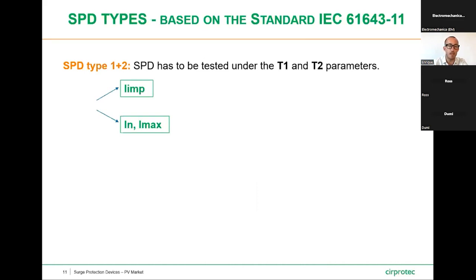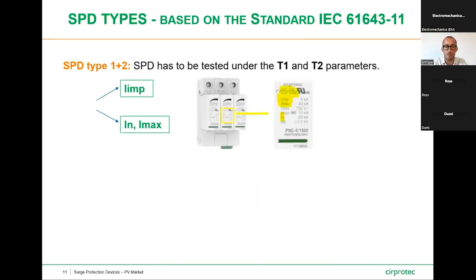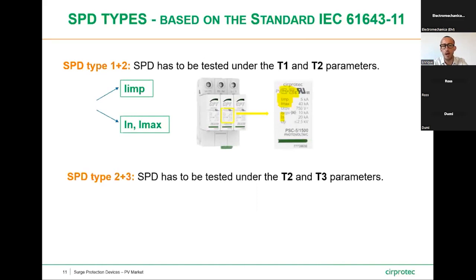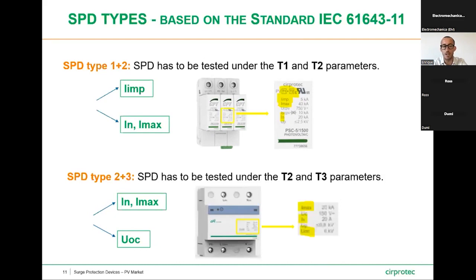For type 1, it should be shared and tested under the IGIMP, and for the type 2, the SPD type 1 plus 2 should be shared the IN and the IMAX into the SPD. Then we do have the SPDs type 2 plus 3, which has to be tested under the type 2 and type 3 parameters. In and Imax for the type 2, and the UOC for the type 3.